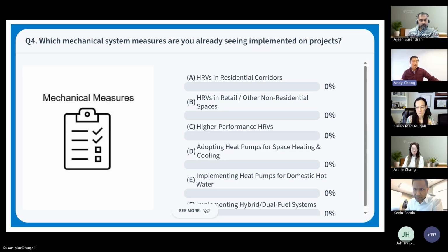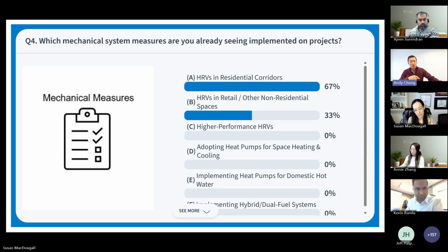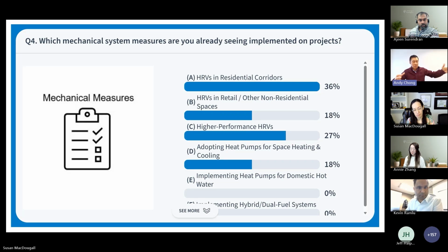That's not to say that's a bad thing on hot water tanks or heat pump hot water. If we switch our hot water plants from gas-based to heat pump-based, my recommendation is you need more storage. So naturally, more cylinders of hot water sitting in a mechanical room means more heat loss coming off those jackets.